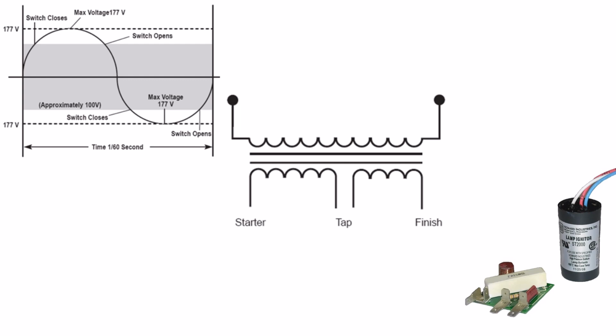Here's how the voltage behaves. Before the lamp starts, voltage is about 110 to 120 volts. Right after startup, voltage drops to 15 volts. After a few minutes, as the lamp warms up, it climbs to a steady 44 to 62 volts, depending on the model. Here's something to remember. Once the voltage drops below 100 volts, the starter cannot operate anymore. That's by design. It prevents the starter from sending high voltage spikes while the lamp is already running.